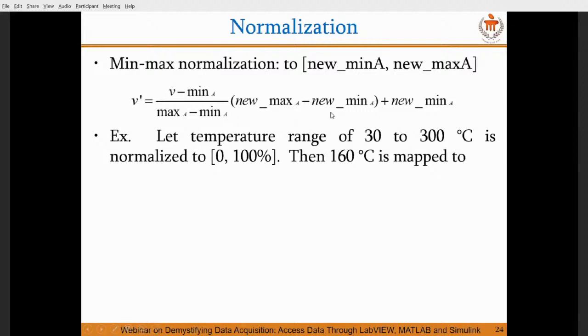This formula is going to be used repetitively; later I will give an example on a case study. So the new value I want to find is for 160 minus the least value, 30, divided by the range, 300 minus 30, multiplied by the range you want to convert to, so 100 as the maximum value minus 0 as the minimum value, plus the offset as 0. So in a 30 to 300 range, 160 degrees is going to be represented as 48.148%.